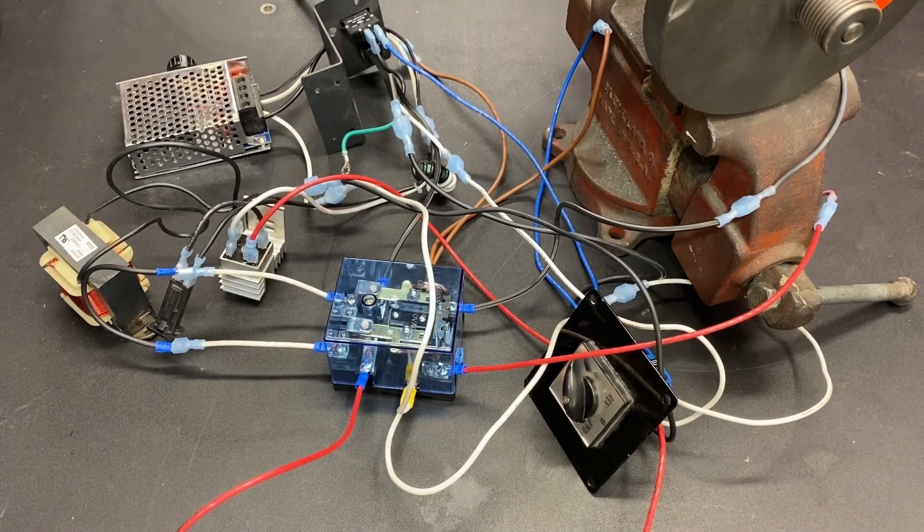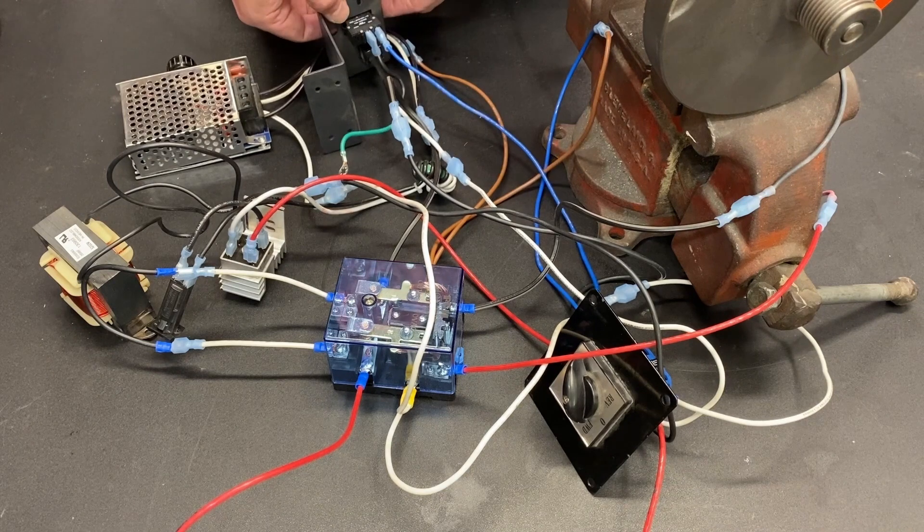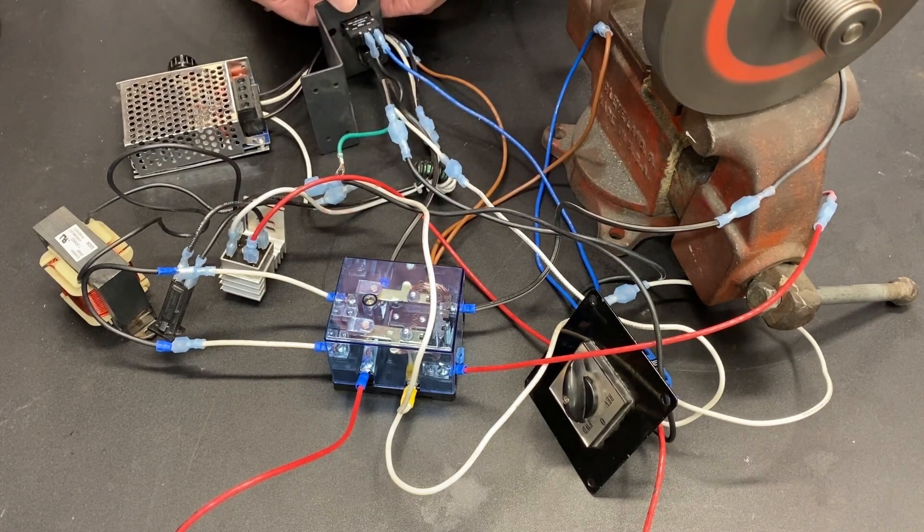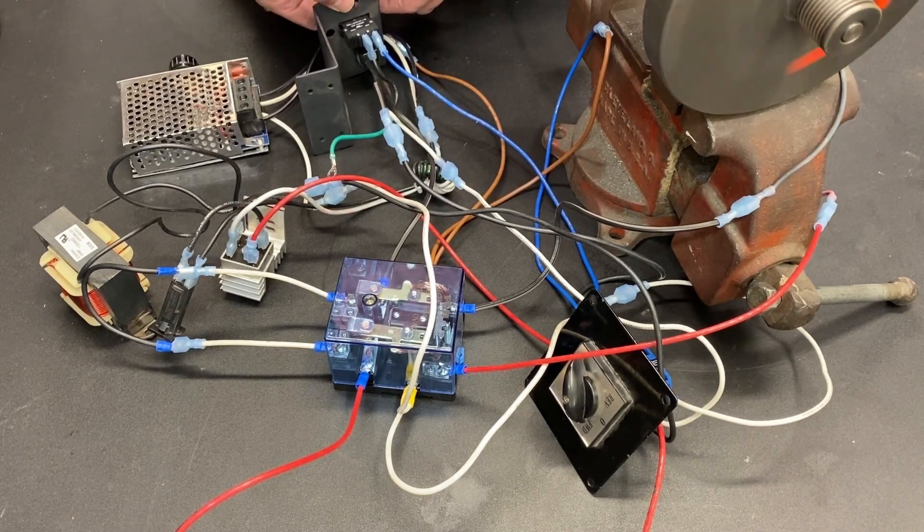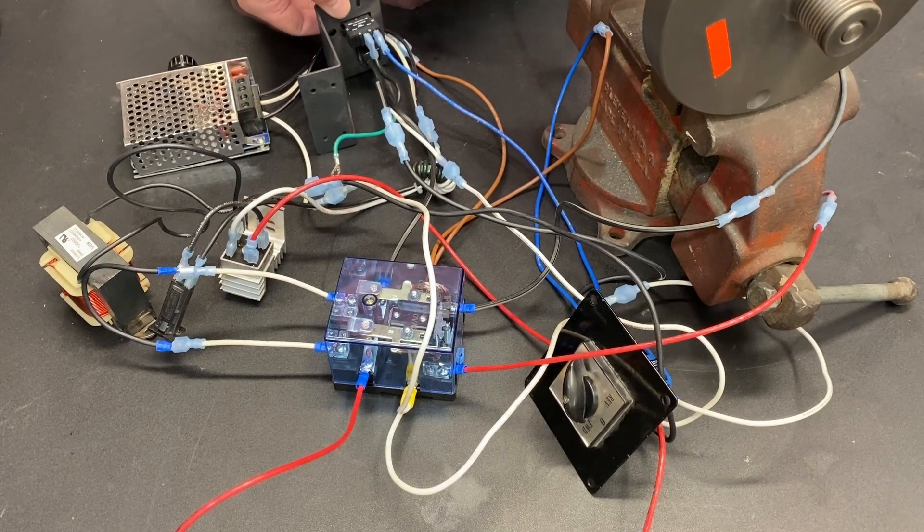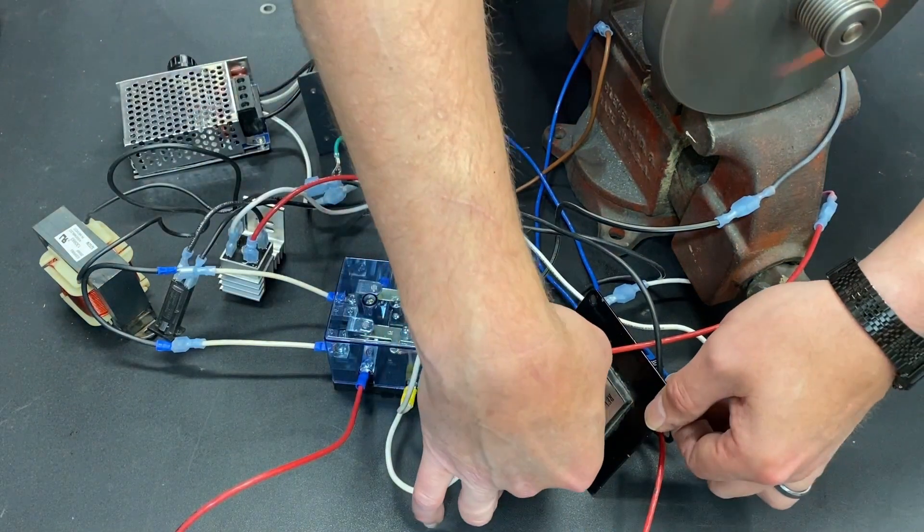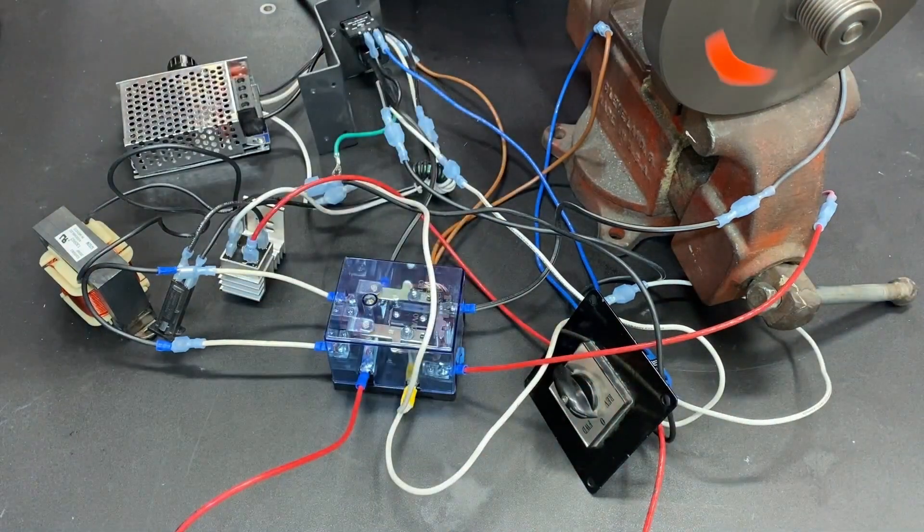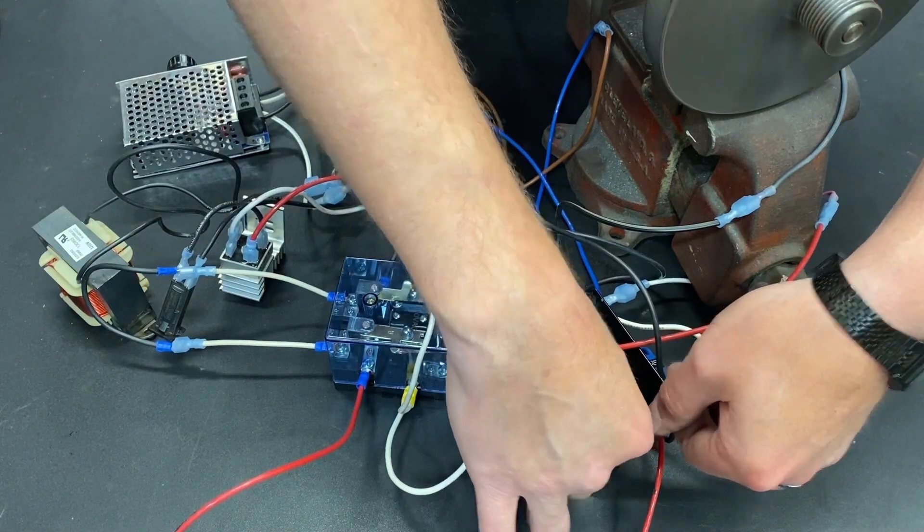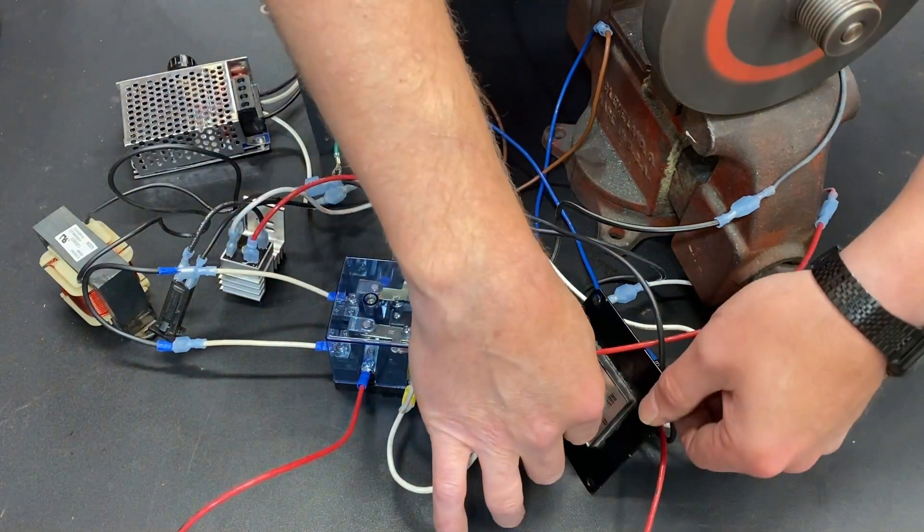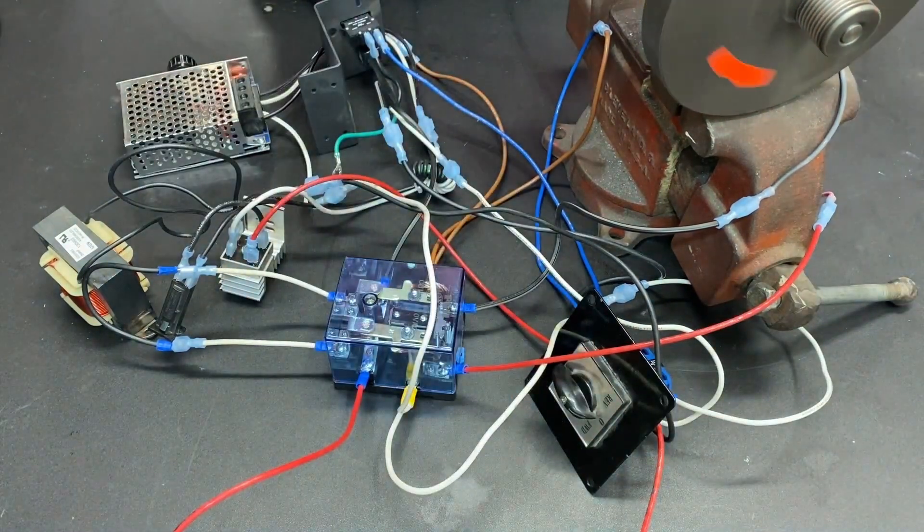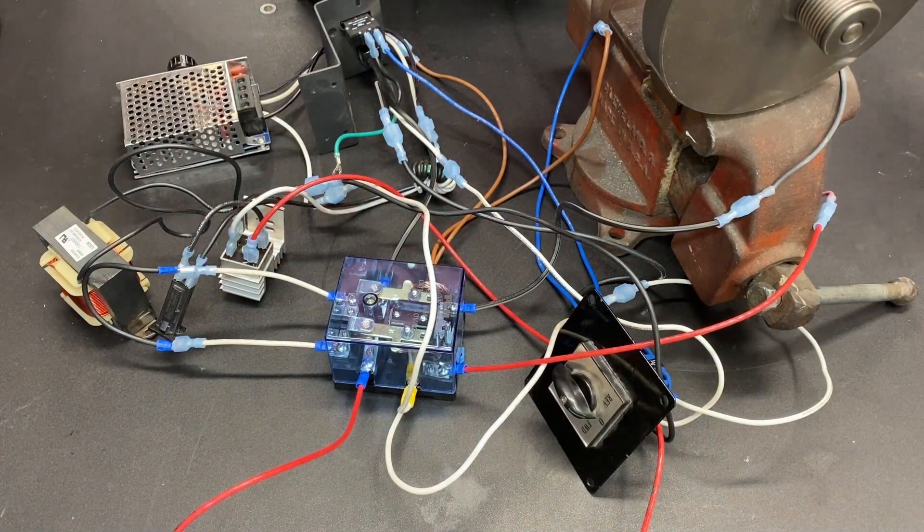So here's the bench test with the motor. Comes on. We cut main power. Brake engages. We turn it to the off position on the direction control. Brake engages. We turn it to reverse. Turn it off. Brake engages. So this is a fantastic setup.